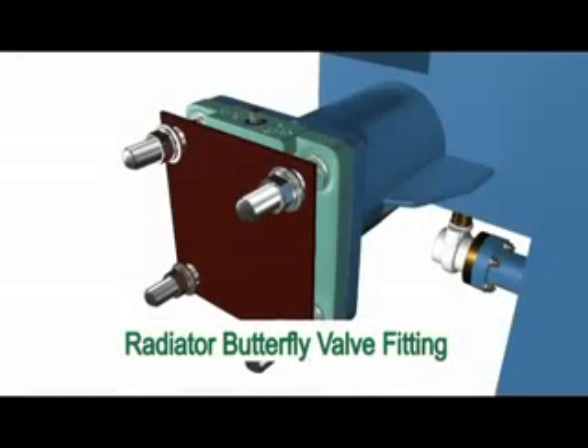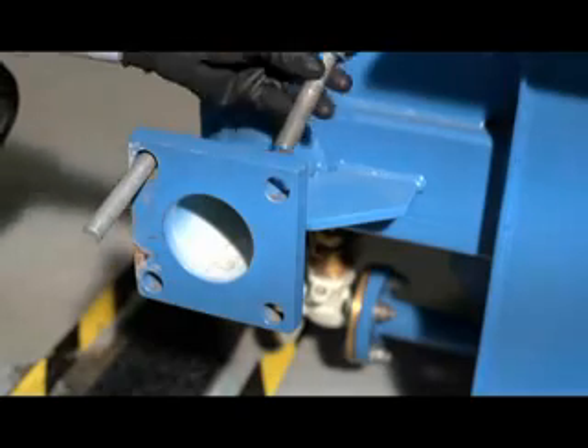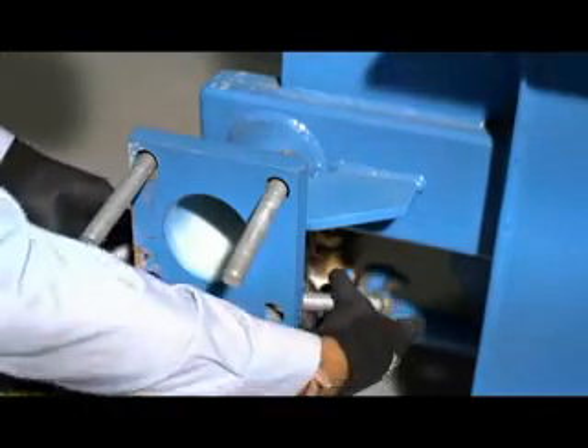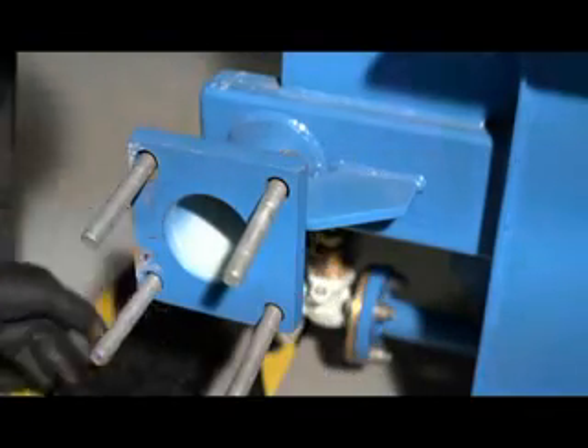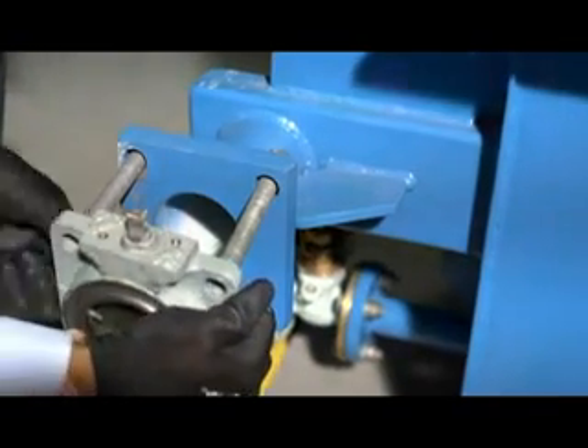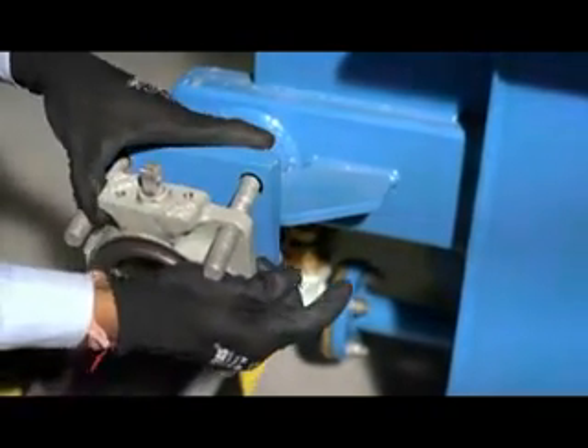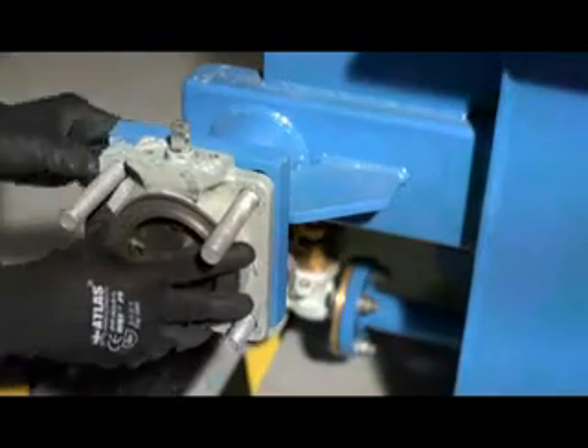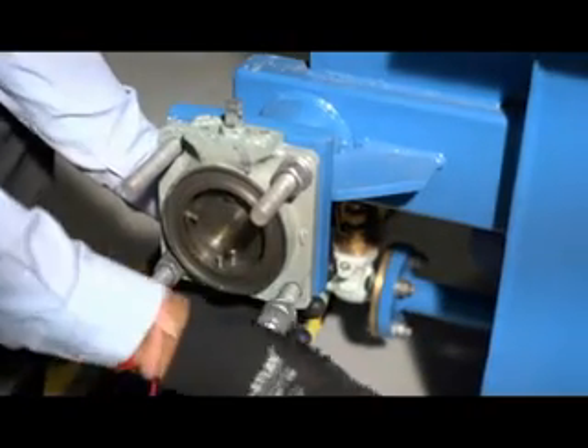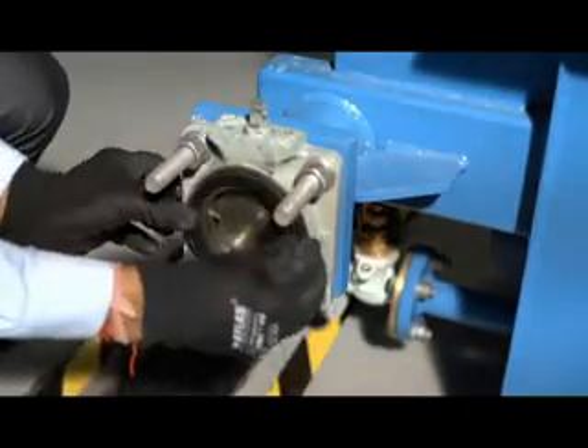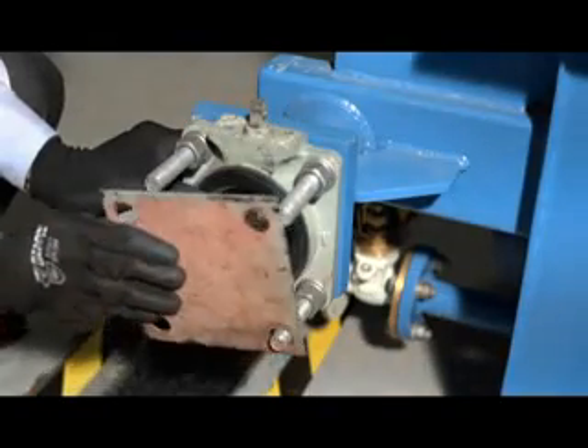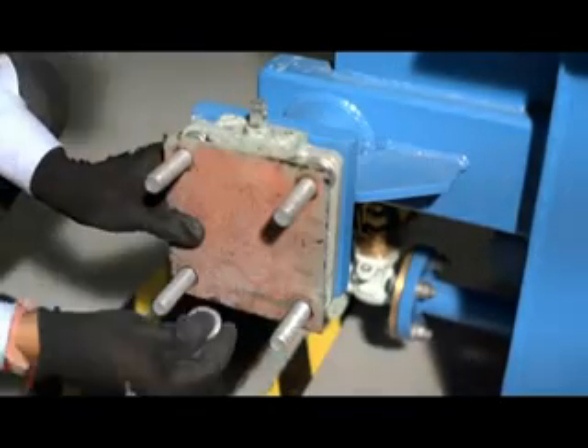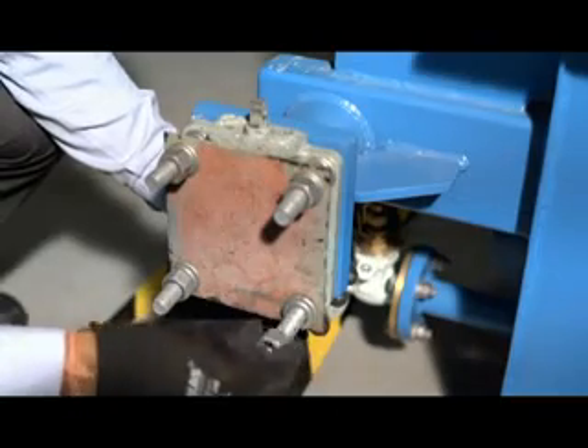Radiator butterfly valve fitting. Butterfly valves provide flow path to the transformer oil for cooling purpose during the service condition of the transformer. Normally it is closed during transportation or storage of transformer. There are 2 modes in this butterfly valve, that is open and shut. At the time of the radiator fitting, oil filling and transformer in service condition, it is in open mode as per arrow mark.